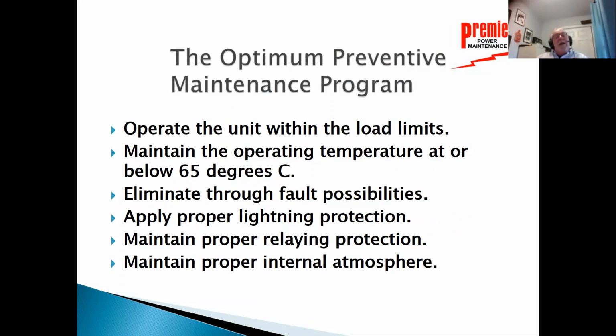So if I look at a transformer, we can talk about really in-depth maintenance programs, but if I want to talk about a preventive program, here is the preventive program. Operate that unit within the proper load limits. I can very well remember a summertime, this would have been 40 years ago in my career. It was a really hot summer. We lost a transformer in one of our substations. We had another transformer in that substation, and we picked up the load on another transformer, but it was extremely overloaded. And we're actually out in the sub yard with a hose spraying water on the radiator fins of that transformer to try to keep the temperature down.